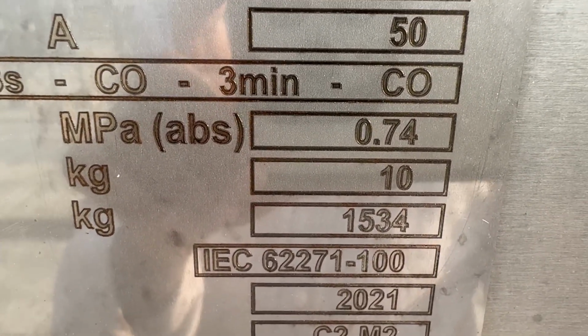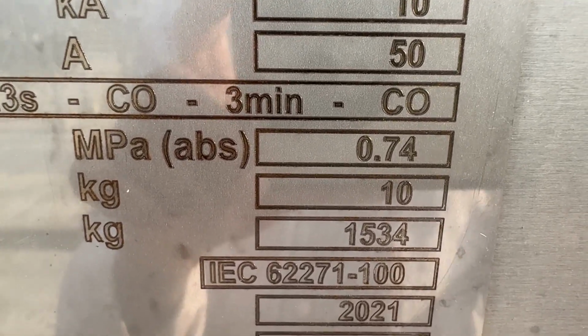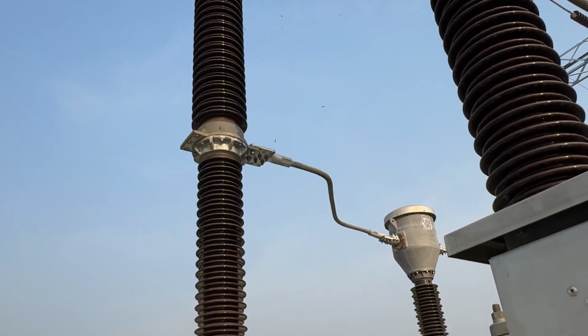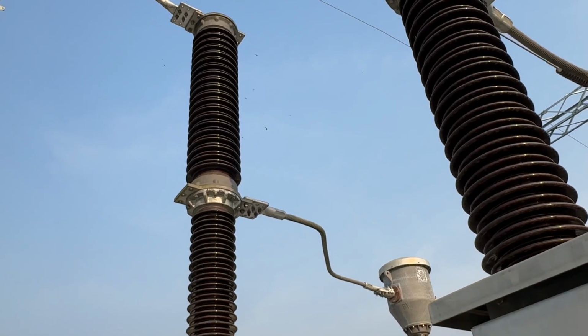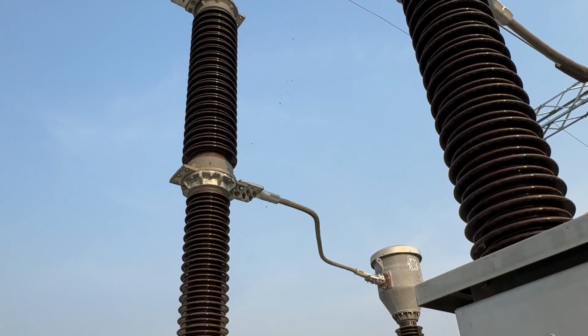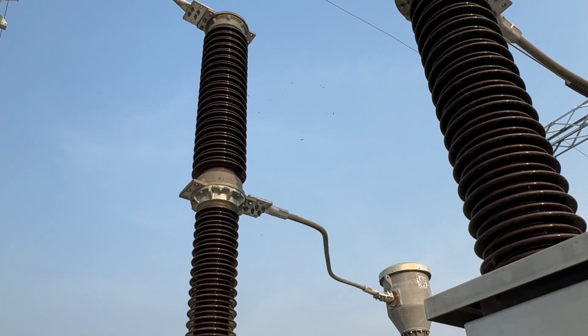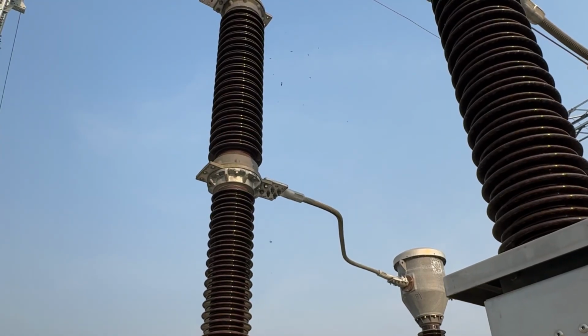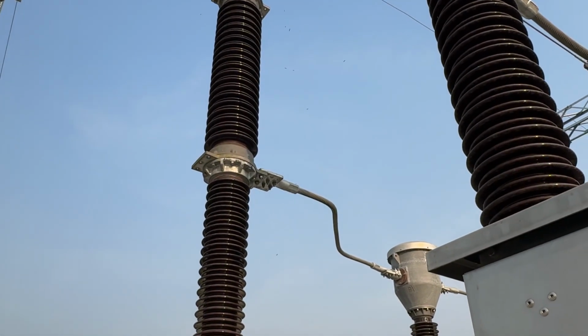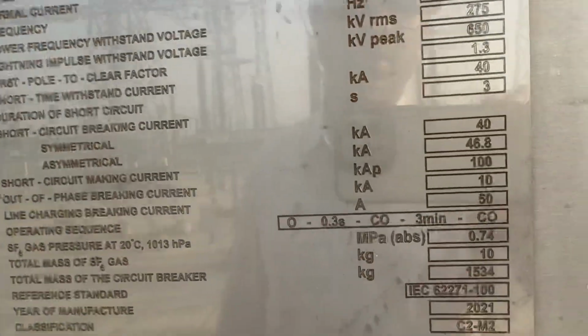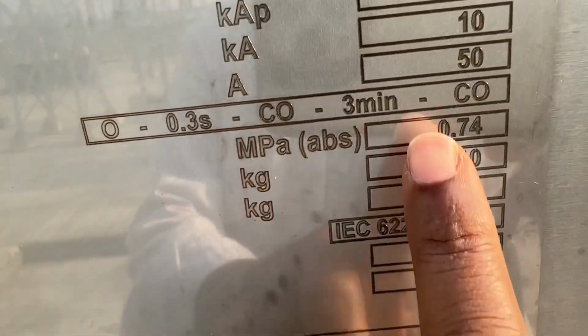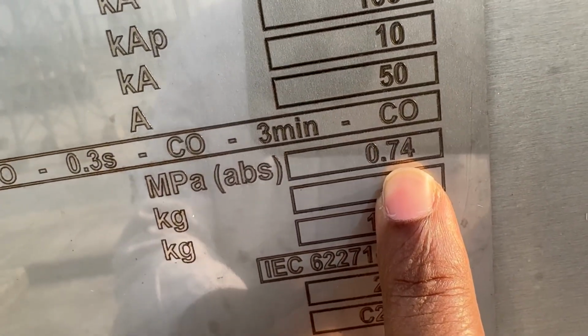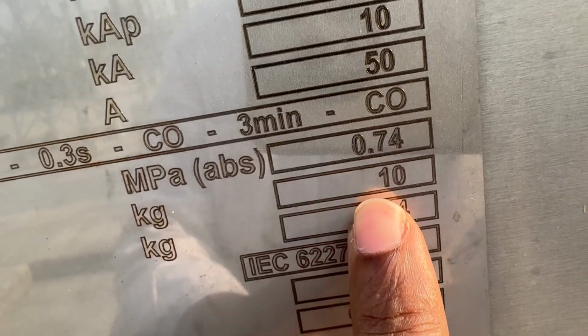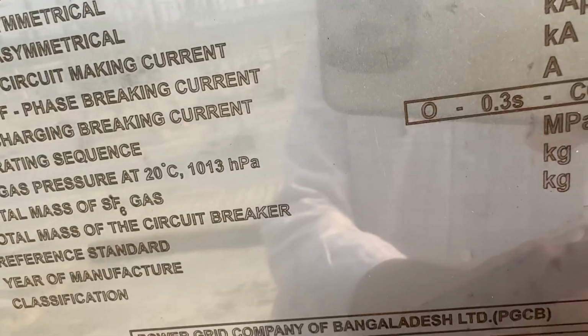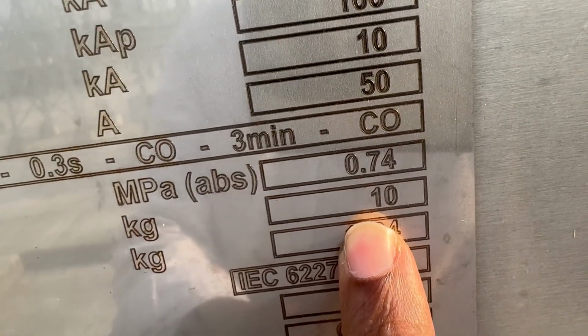MPa, absolute. This is the SF6 gas pressure. We know that in this circuit breaker, the insulation between the two contacts when the breaker is normally open is maintained by SF6 gas. This gas pressure is given here: 0.7 MPa absolute. The total mass of SF6 gas is approximately 10 kg.